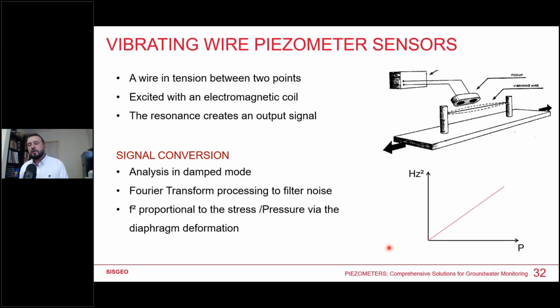Now, about the vibrating wire piezometer sensor. I'm sure many of you already know this principle, but I will just sum up. This is a wire which is in tension between 2 points, and this wire is excited by means of an electromagnetic coil. The resonance creates an output signal. To put it in easy words, this is the same as a violin string or a guitar string. When the guitar string is extended in tension, and you pinch it or excite it, you get a sound. So the analysis is then a very complicated signal. It's a vibrating signal. You have to analyze it with a Fourier transform in order to process and filter the noise.